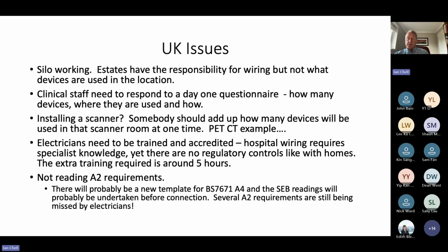I trained a hospital last year, and as part of that training, I looked at a PET CT scanner to do a mock compliance test, and it failed. I went through the process of how they had worked out what devices in the room were to be used, and they didn't do that. The big omission was that no sockets or earth studs were fitted at the head end of the scanner, because nobody had worked out where all the devices were going and how many would be used. Okay, it still goes on.